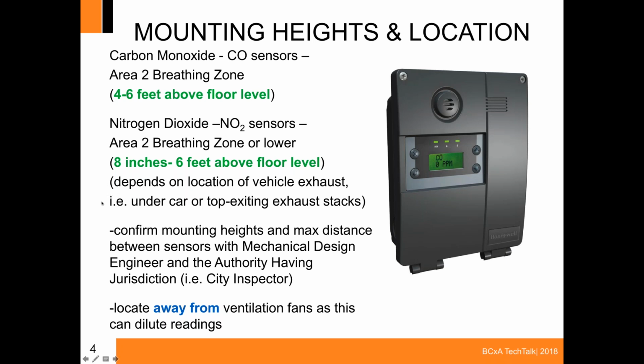It's important to confirm your mounting heights and the maximum distance between the sensors in the parkade or parking garage with the mechanical design engineer and your city inspector or authority having jurisdiction. We quite often see on design reviews that the mechanical design drawings are just showing a sample of what sensors are required, and not necessarily getting the proper distance. And the last thing you want is to have more sensors added when the city inspector comes in, which actually did happen at our REMI art gallery. You do want to make sure that you locate these away from any ventilation fans, so that when they're reading the CO or the NO2, it is not being diluted and giving you not the exact value that is actually in the parking garage.